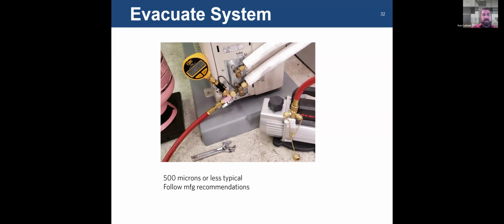You shut off the valve at the vacuum pump, or if you've got a valve in line like they do over here, you can shut off that valve, and you watch your micron gauge. Oftentimes your 500 microns will go up once you shut that vacuum pump off. You close the valve, and your microns will go up. The manufacturer usually will give you a guideline as to what's acceptable. Fifteen minutes below 1,000 or 30 minutes below 1,000 microns, they'll consider your system tight, and you're good, and you can basically release your charge at that point. And then you can do your startup from there.